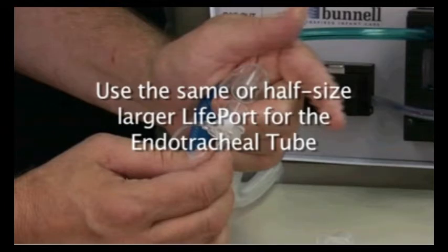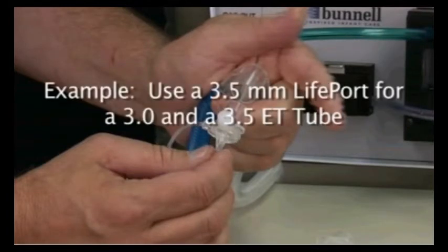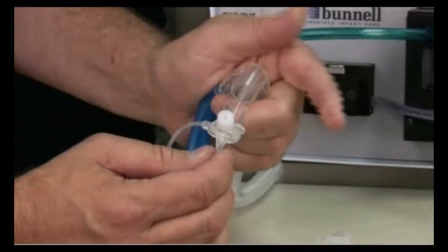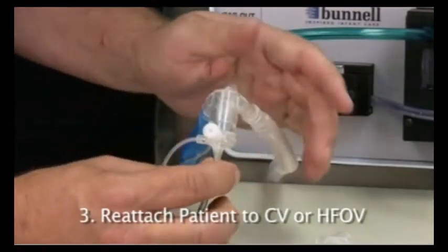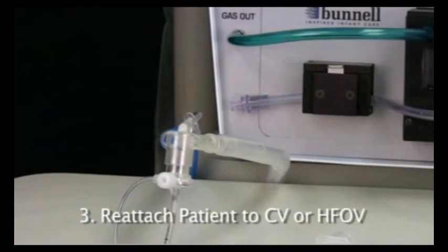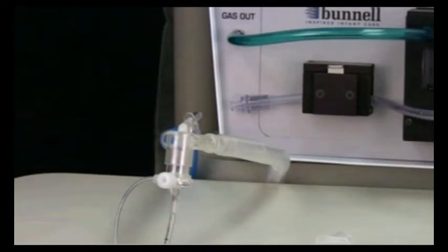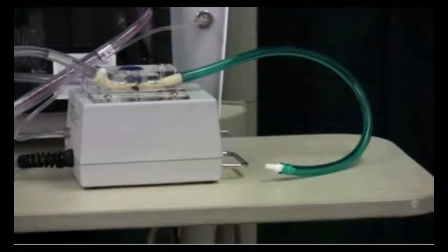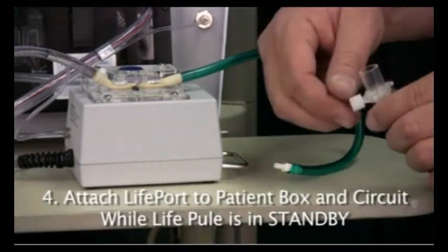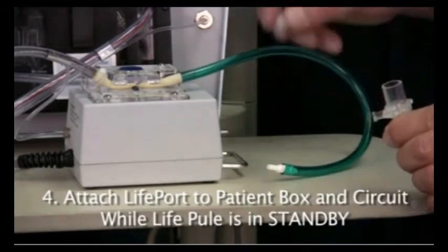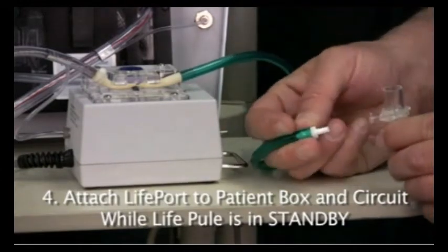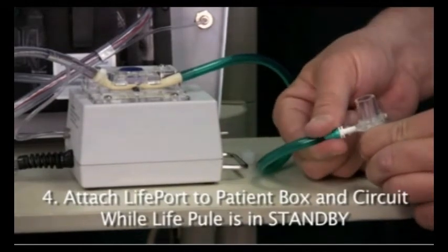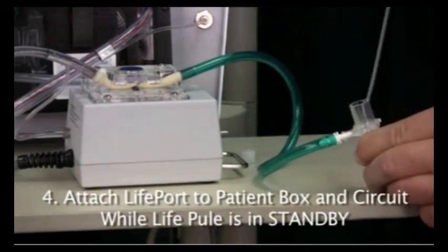The adapters come in sizes 2.5 and 3.5. Therefore, if you have a 3.0 endotracheal tube, you would use the 3.5 adapter. Third, reattach the patient to the conventional ventilator or oscillator. Fourth, once the patient has been stabilized on the conventional ventilator or the oscillator, make the LifePort adapter connections to the patient box and the LifePulse circuit while the LifePulse is in the standby mode.